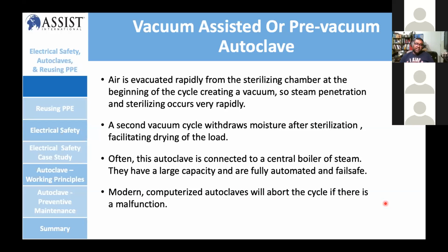Most of these autoclaves are connected to a central boiler to get the steam, and have larger capacity and are fully automated and fail-safe. Normally you're going to see the bigger units in the CSSD or a similar department that does sterilization, all that. Most of them nowadays use computerized autoclaves, and you can do the cycling and setting up all that. Sometimes you can abort the function of that. So the controller is also very important. You need to make sure that you check that all the controllers are working properly.